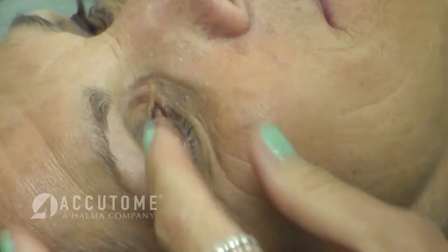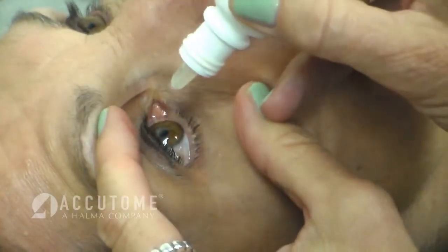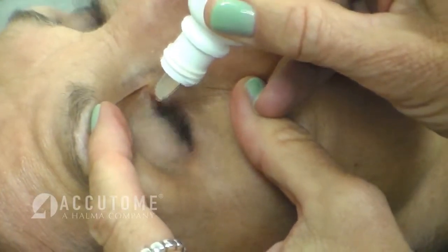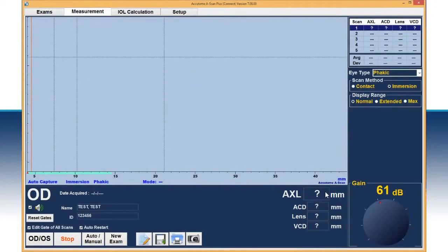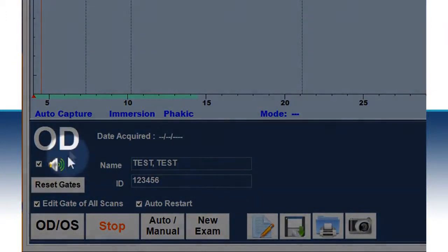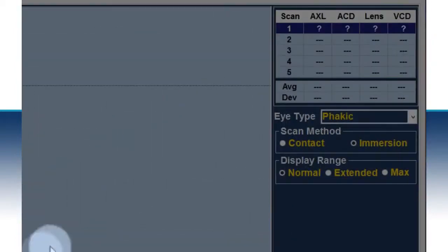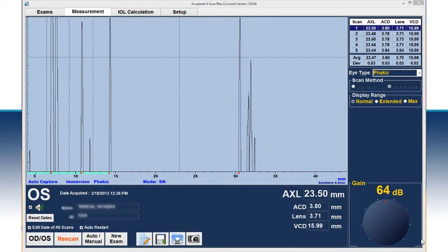Recline the patient and administer the anesthetic drops in the upper and lower part of the eye. Once the drops are in the eye, prepare for the test by verifying that all measurement screen settings are correct. Confirm that the proper eye is selected, OD/OS. Proper measurement type is selected, auto or manual. Correct eye type is selected, and also that the type of scan is correct, contact or immersion.